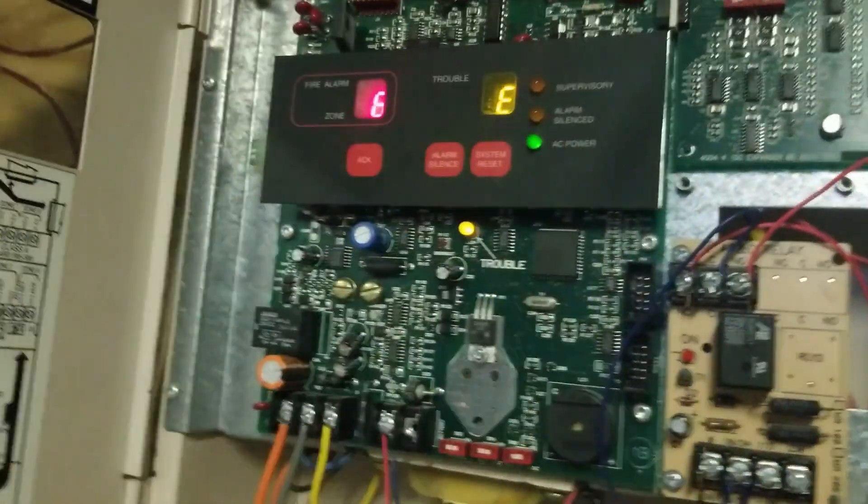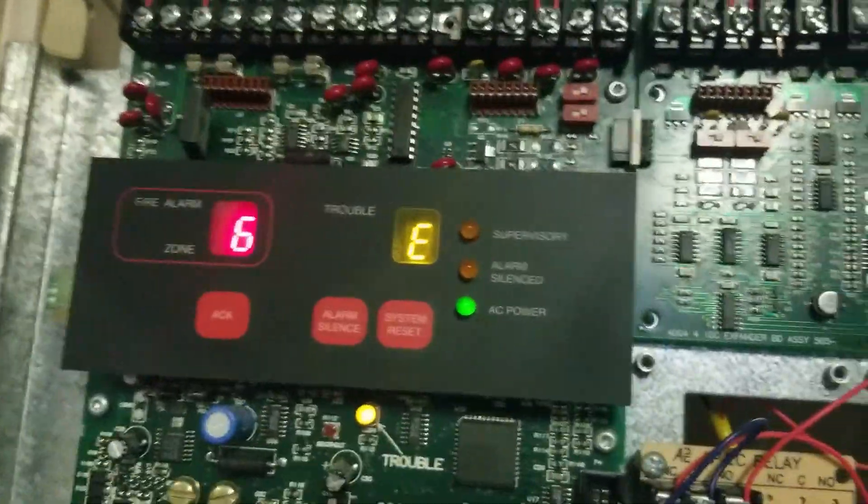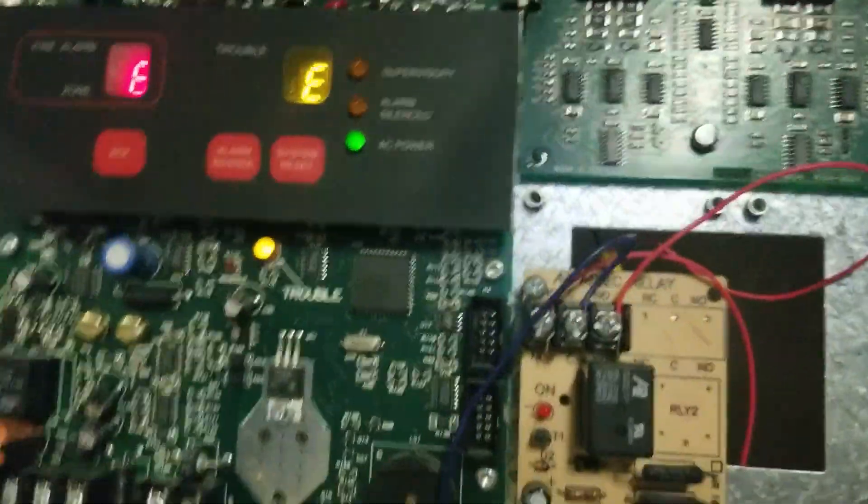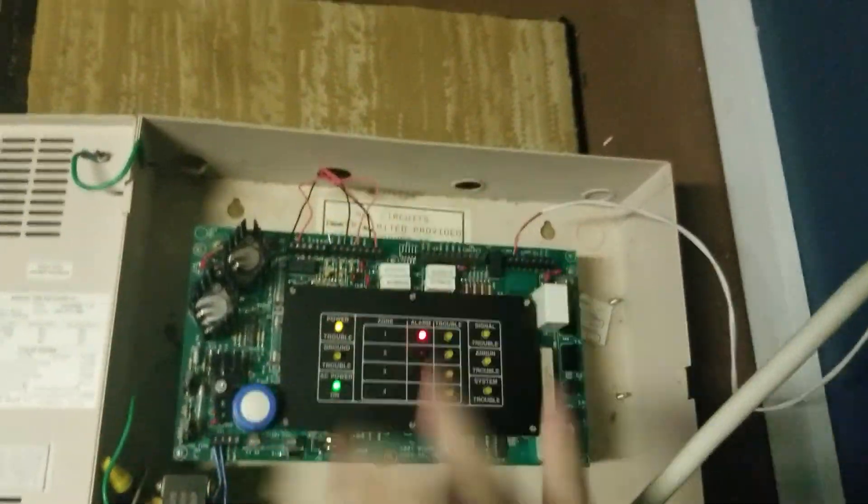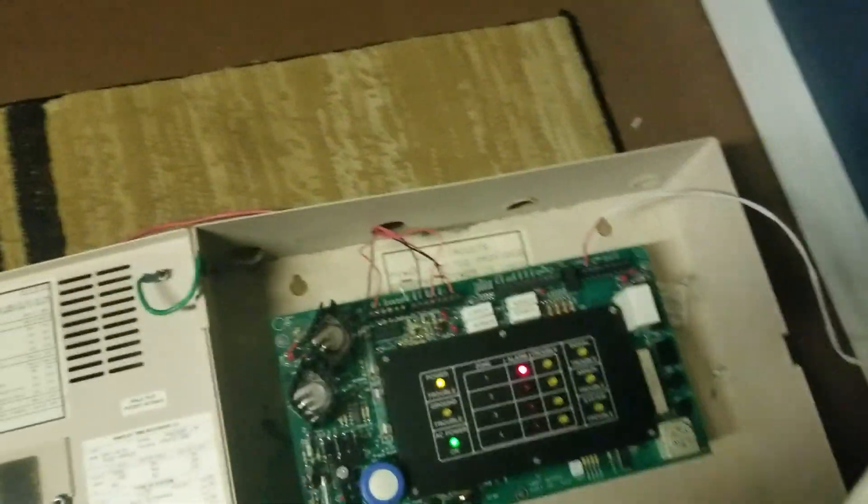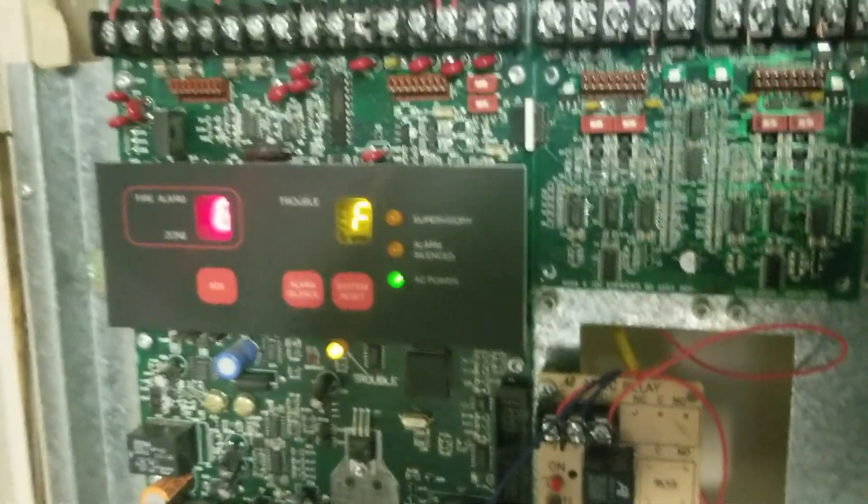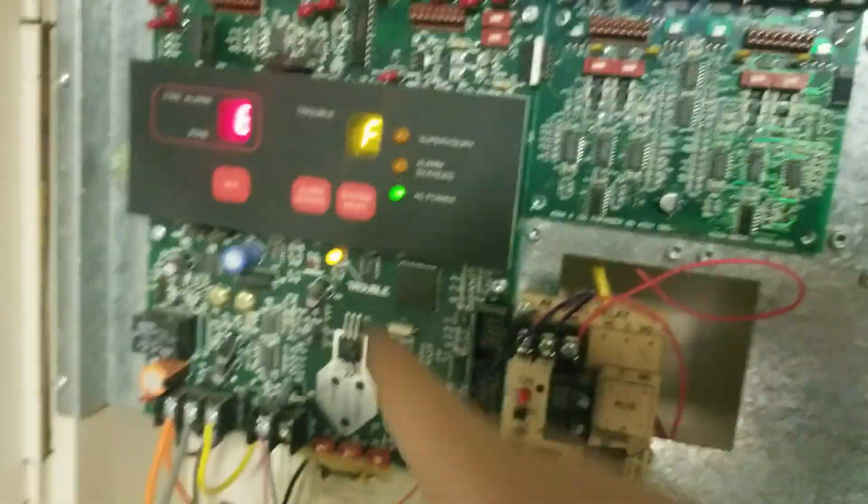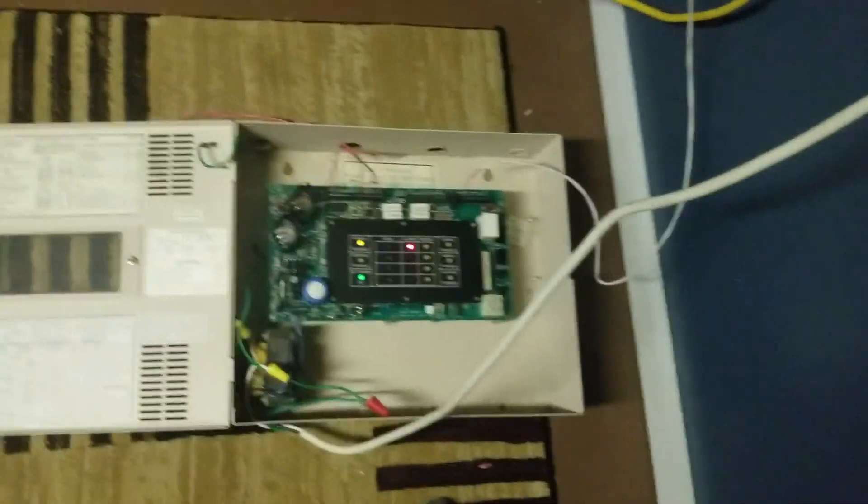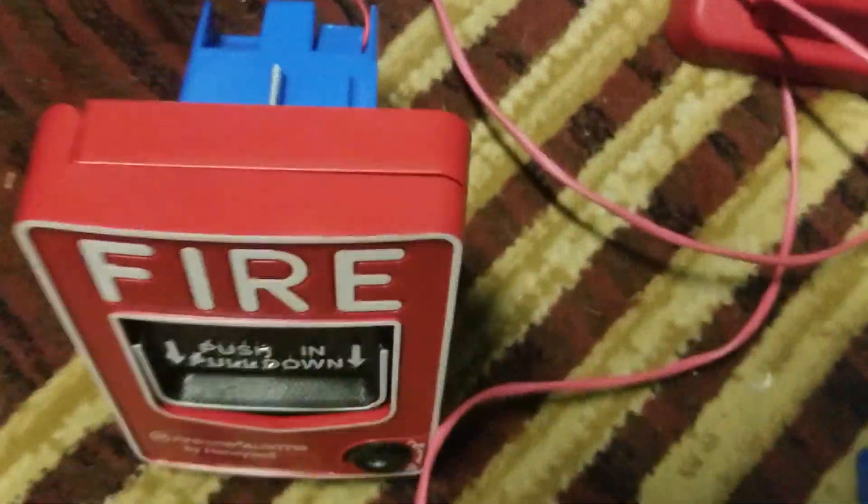Yep, that's that. Let me acknowledge up here, we have a zone six fire alarm condition on this because we have an alarm condition on this. We won't be able to reset this quite yet because this is still an alarm, and won't be able to reset that without resetting this station first.